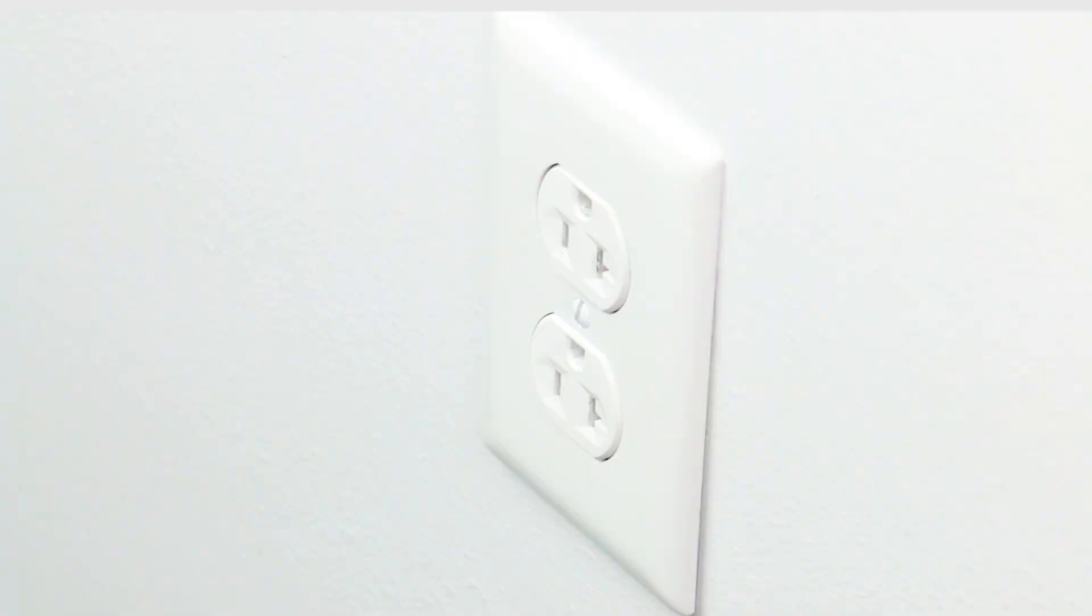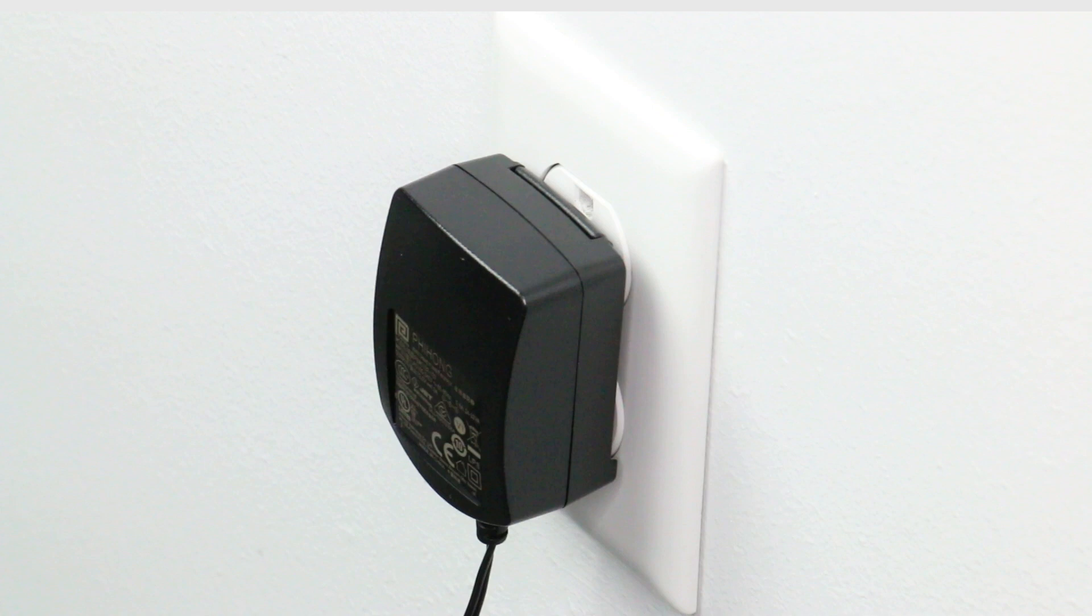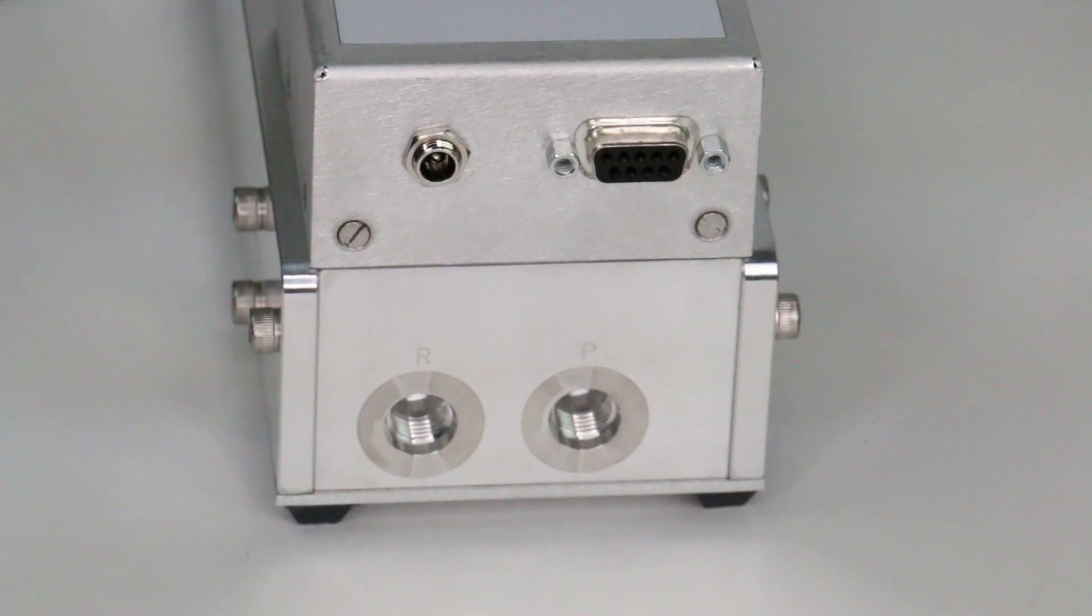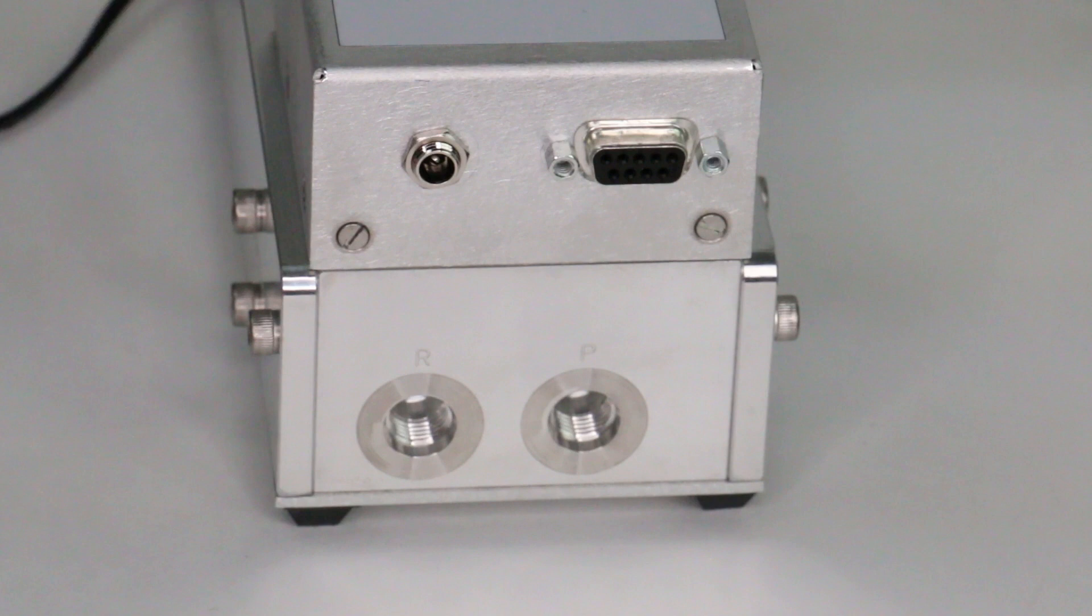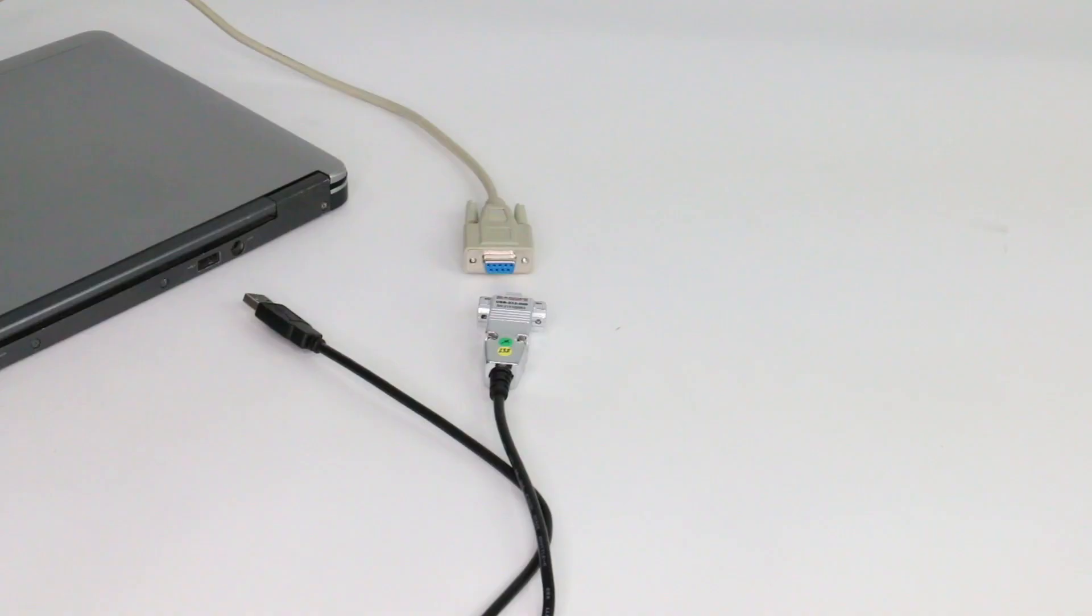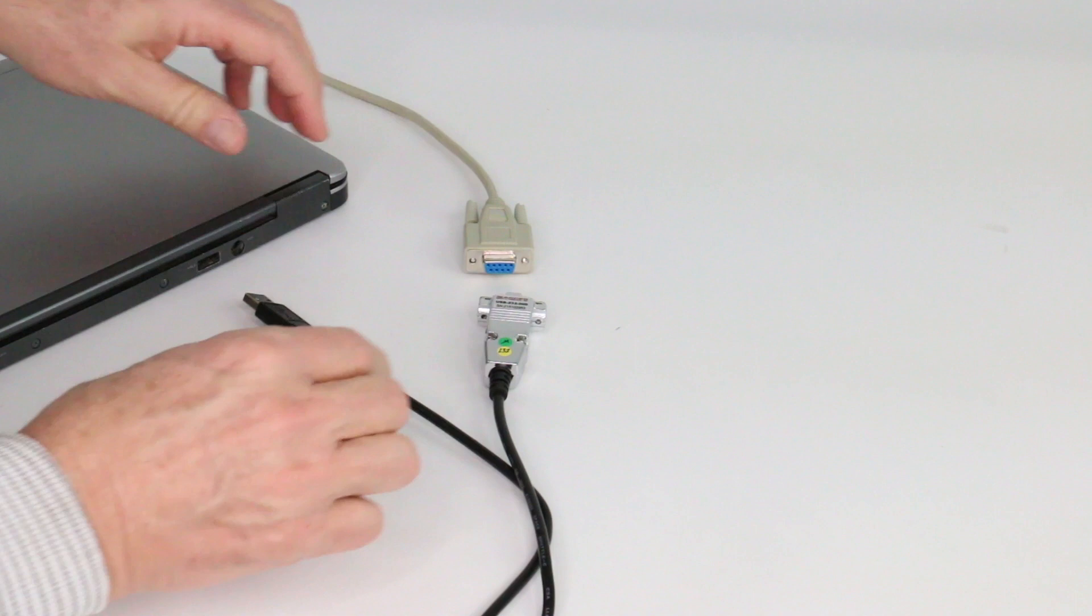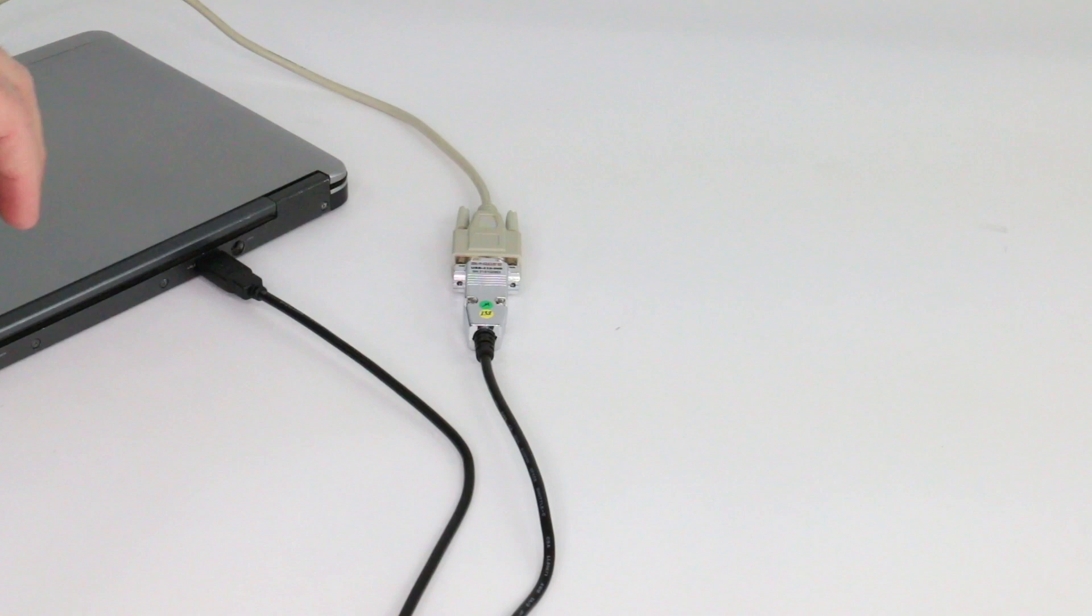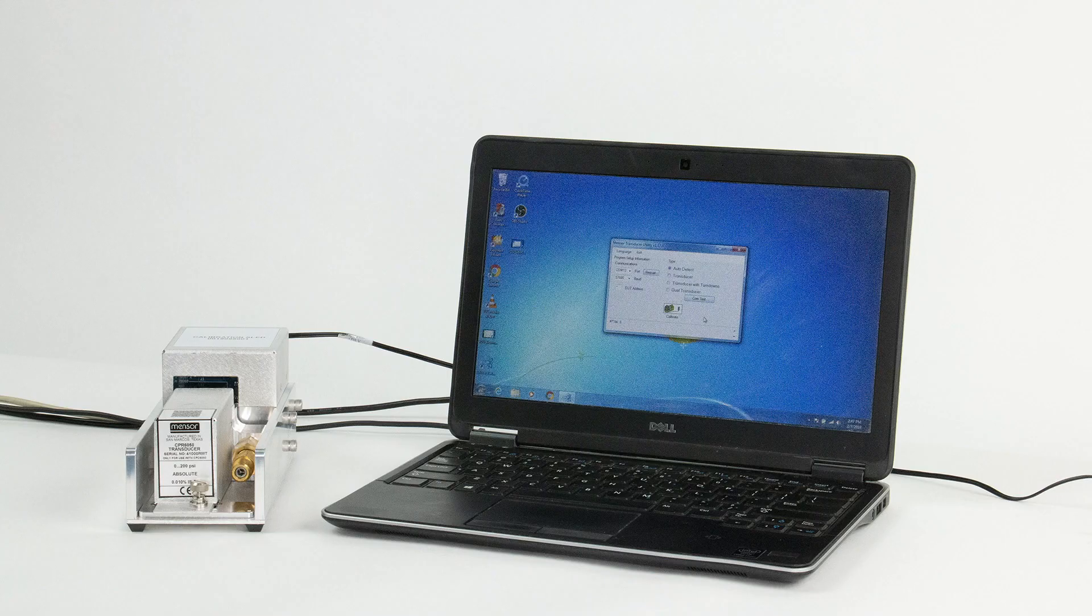For a transducer that uses a calibration sled, connect the AC adapter of the power supply to an AC power socket. Then, connect the power supply to the circular power connector on the rear of the calibration sled. Connect the 9-pin D-sub connector on the calibration sled to any available serial port on the computer, using an adapter if needed.